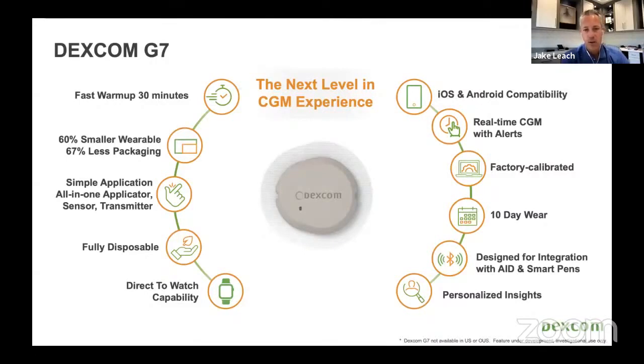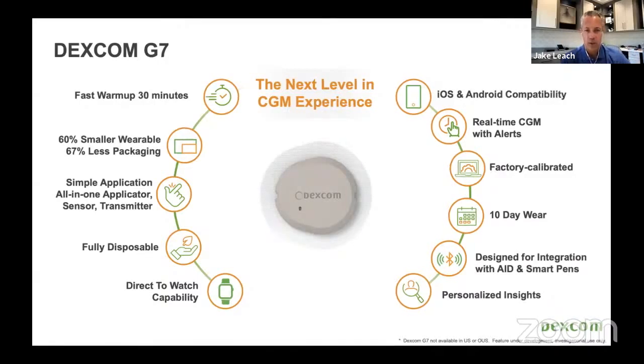The application is all done very simply, with one button press once the applicator's on the body. It's all in one, so the sensor and the electronics are one piece. They don't come apart like they do with G6, where you have the separate disposable and the reusable transmitter. It's all one with G7, and so that system is deployed, and then after 10 days of use, it's peeled off, and another one is adhered, so it's fully disposable.